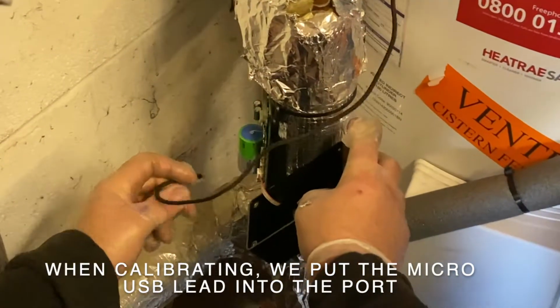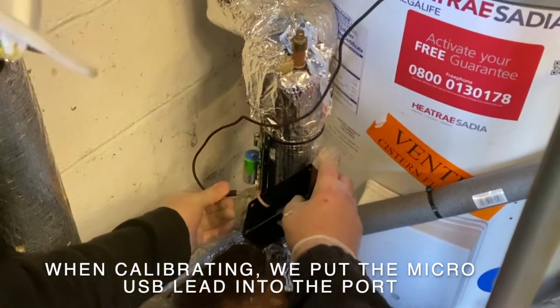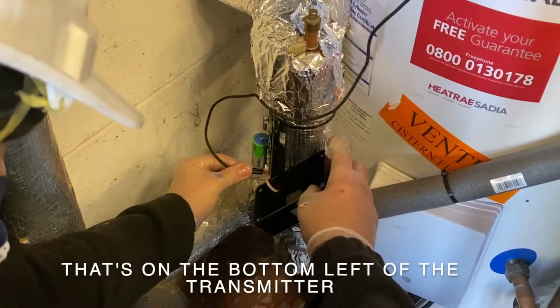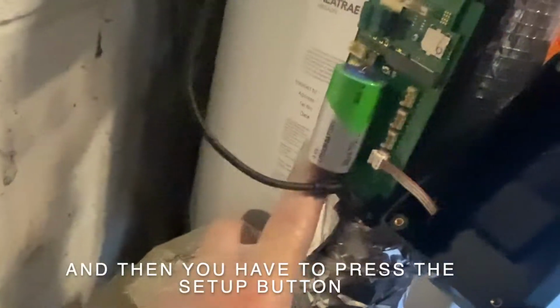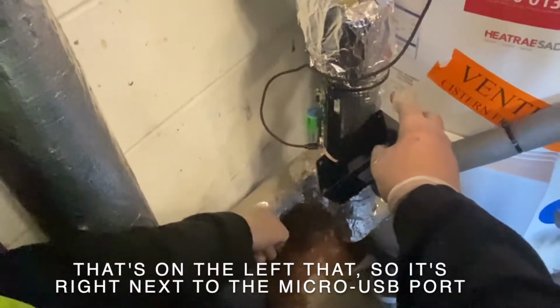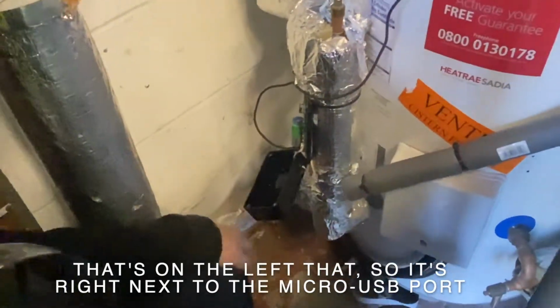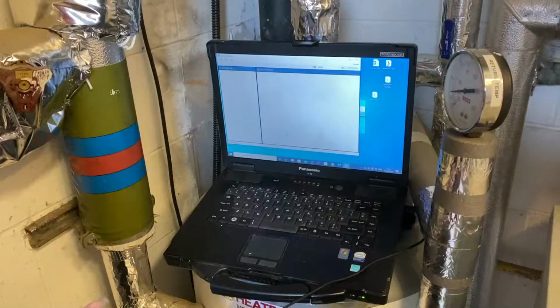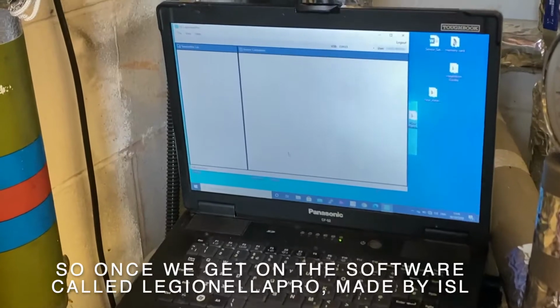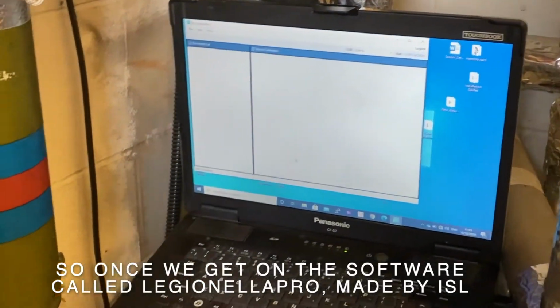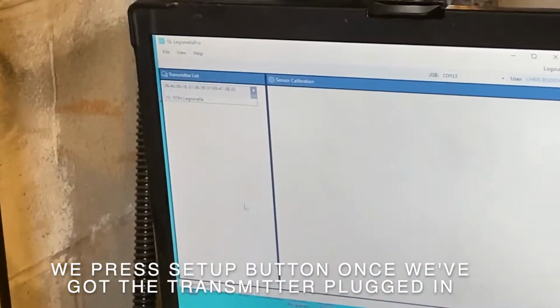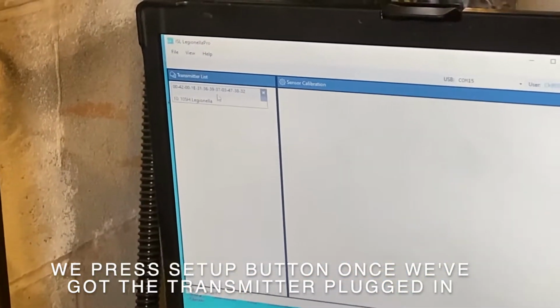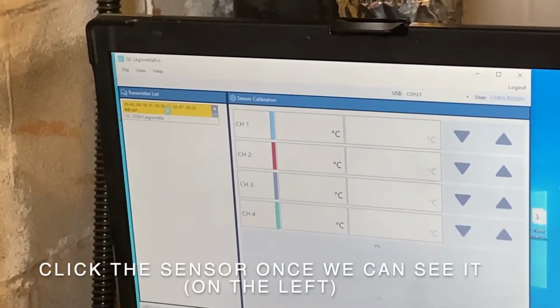At the end, when we're calibrating, we're putting a micro USB into the port that's on the bottom left of the transmitter. And then you have to press the setup button that's on the left of that. So it's right next to the micro USB port. So once we get on the software called Legionella Pro, which was made by Invisible Systems, we press the setup button once we've got the transmitter obviously plugged in. Click the sensor once we can see it.